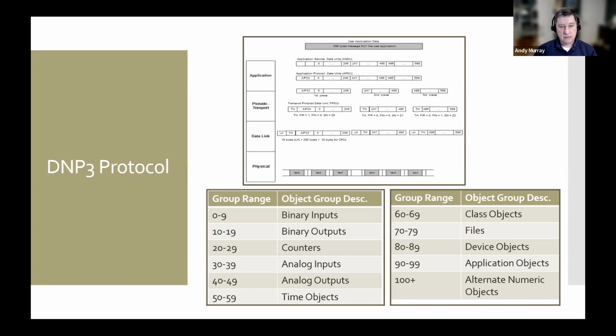DNP also has what they call object groups, very similar to the function codes we talked about in Modbus. You'll have ones for binary inputs, but DNP also has methods for file transfer built into it, and it has the ability to do time syncing built into the protocol itself.